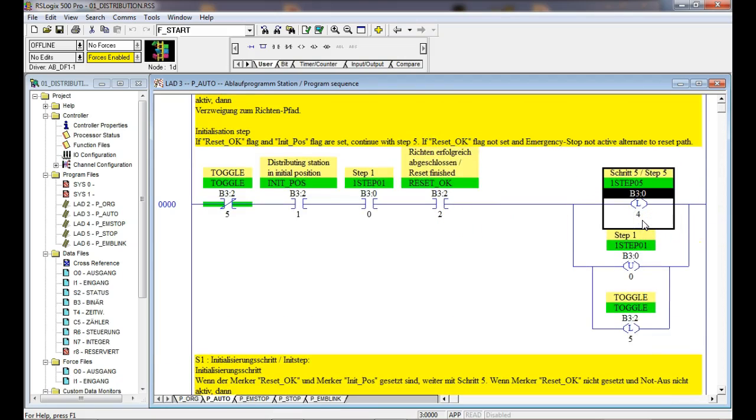Something that we didn't get an opportunity to do, and we should make sure we do this in the intro too, is use an internal bit we call a latching. We teach how to do a seal-in circuit, right? You understand? We could do this with seal-in circuits, but it would be extremely complex because it's going to take one condition to seal it in and another condition to drop it out. Understand that? So it's easier to do with what we call latching relays.